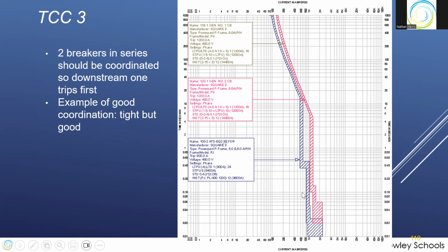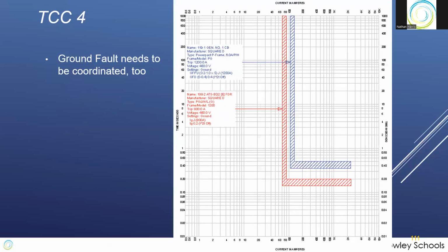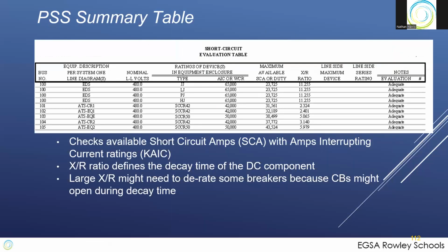Okay, well coordinated. If you give a fault, now the currents along this axis on the left side, I'm sorry, top left axis, currents along the bottom axis. As you go up in current, at this current flow, you'll never trip. At this current flow, you'll trip right here. Okay, so that's what that is, time current curves. When will you trip at what value of current? Ground fault is checked as well. And a summary table is created with all these values in here.